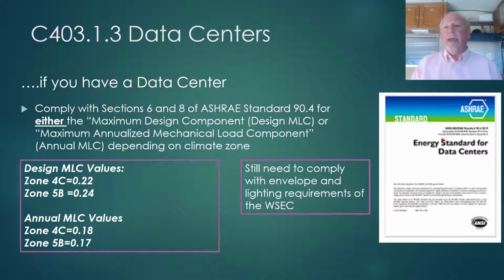An alternate path is to use a maximum annual mechanical load component. This annualized load component compares the efficiency or the load of the HVAC system at different load conditions divided by the IT load at different load conditions. And so this is an average HVAC load at 25%, 50%, 75%, and 100% load divided by the average IT load at 25%, 50%, 75%, and 100% load. So it's similar to that SEER rating, or seasonal energy efficiency ratio, on air conditioning units. So if you use the annualized mechanical load component, then in 4C you cannot exceed a ratio of 0.18, and in 5B you can't exceed a ratio of 0.17.